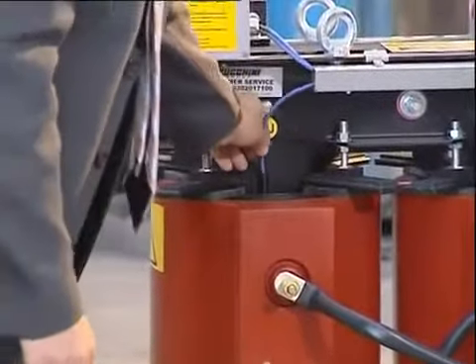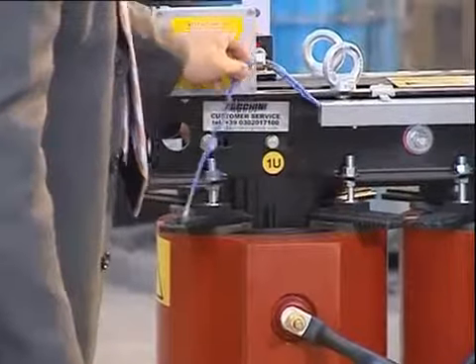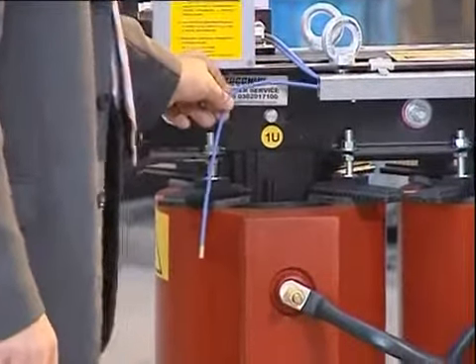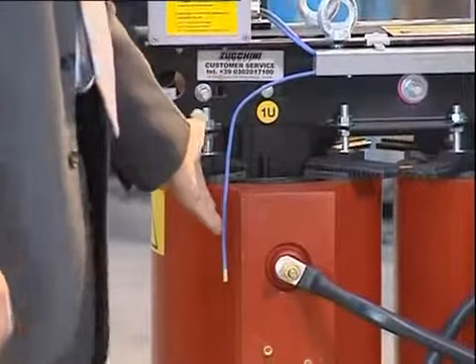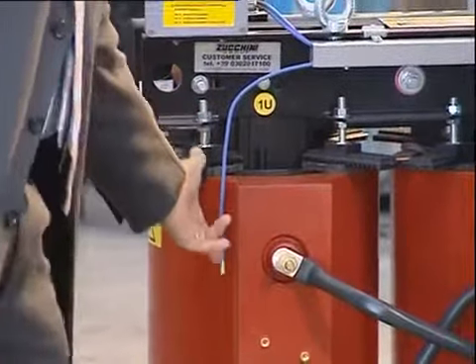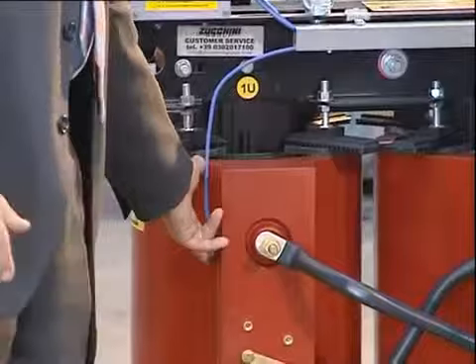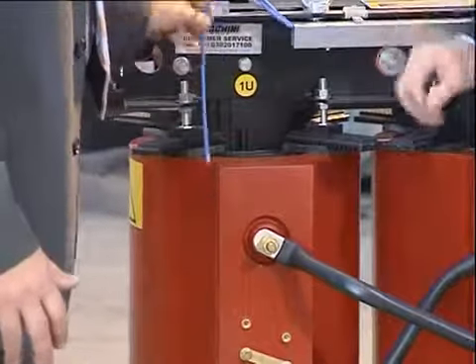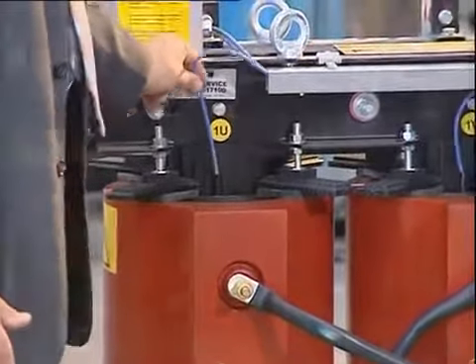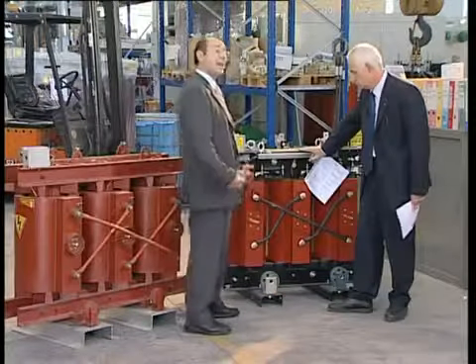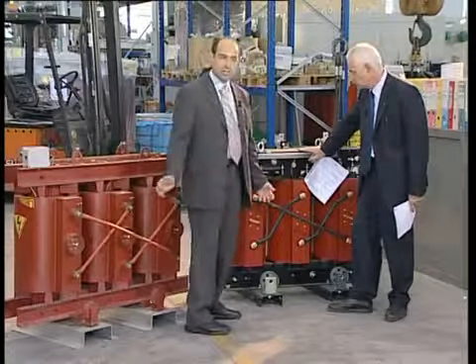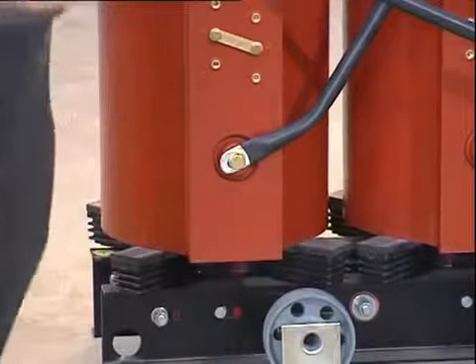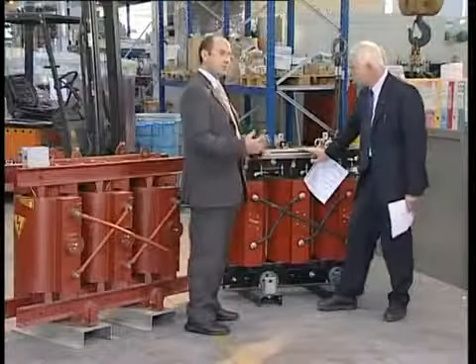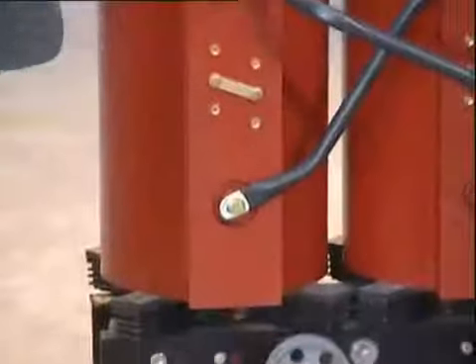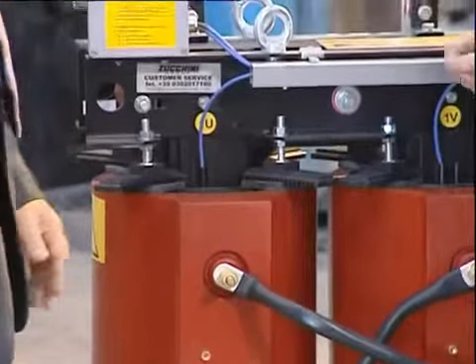What's this? This is a PT100 probe, used to detect the low-voltage winding temperature. As you can see, we have installed it in the hottest point of the transformer. Let's call it the critical point. Does everybody do so? Not exactly. I must say that many of our competitors, including the most qualified ones among those represented here, install the probe at this height. Where it is colder. Sure, where the temperature is considerably lower, and as a consequence the display shows a lower temperature. So one needs to pay attention to this aspect.